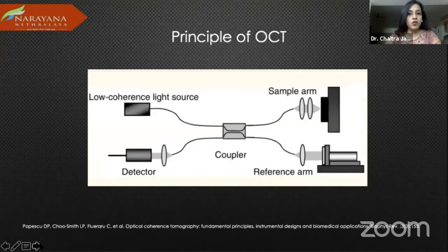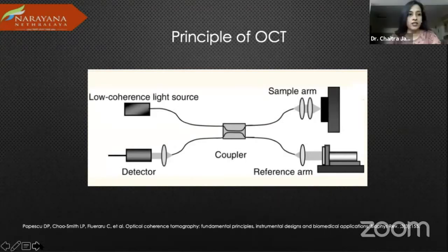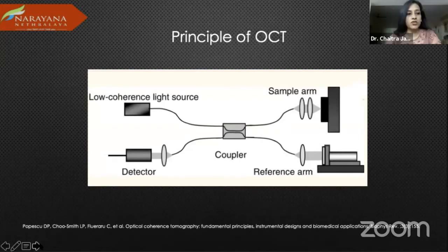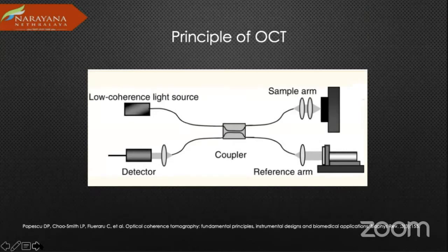Coming to the principle of OCT itself, it is like an optical analog of ultrasound imaging that uses low coherence interferometry to produce cross-sectional images of the retina. It uses infrared light from a superluminescent diode that is divided into two parts — one reflected from a reference mirror and the other scattered from the biological tissue. These two are then reflected to produce the interference pattern, the echo, and multiple A-scans are collated to get a good two-dimensional image.